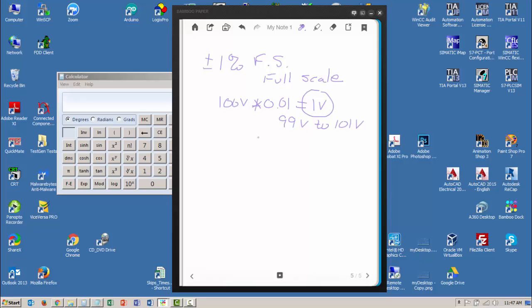through to all of my readings on that scale. So if I'm reading 50 volts on the 100-volt scale, that's going to be plus or minus 1 volt, which is the tolerance at full scale.